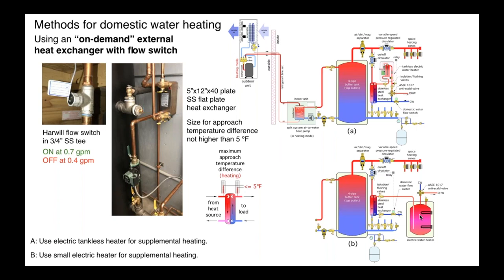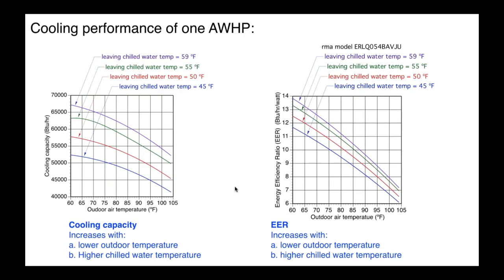Again, if you're sizing that heat exchanger, the biggest heat exchanger you can afford might be a good rule of thumb. You're trying to keep that approach temperature difference no higher than 5 degrees. The lower you can keep it, the more preheating effect you're going to get. So again, there's four or five different ways to incorporate domestic hot water. Now let's briefly talk about chill water cooling.